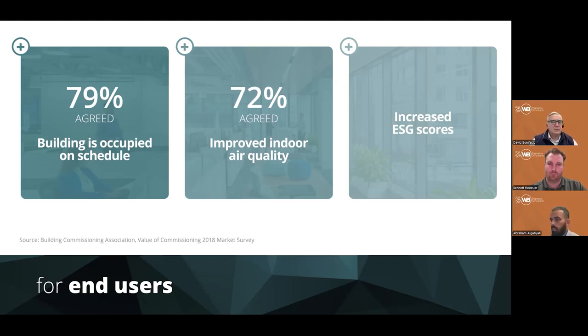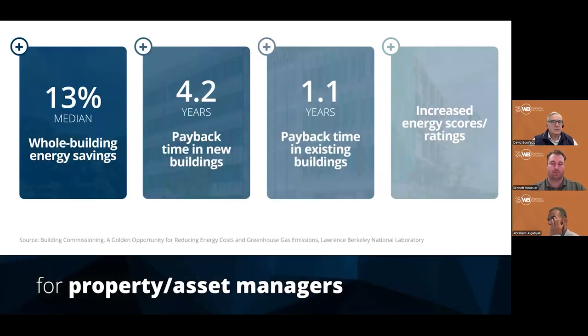For property or asset managers, on average there's a 13% energy savings when commissioning is performed. Considering most energy consumption comes from MEP systems, a 13% reduction is significant. The average payback is approximately 4 years, a very attractive rate of return, and it drops to 1 to 1.5 years for commissioning of existing systems, or retro-commissioning, making it even more attractive.